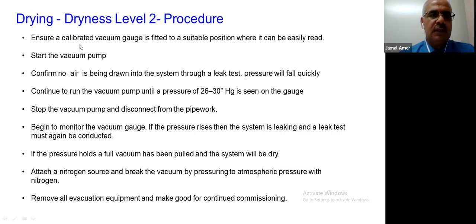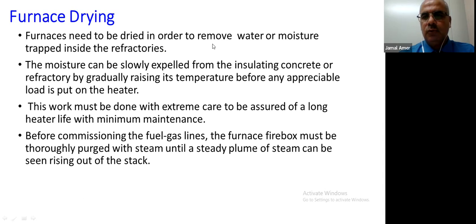Furnace drying. Here regarding furnace drying, the furnace needs to be dried in order to remove water or moisture trapped inside the refractories. The moisture can be slowly expelled from the insulating concrete or refractory by gradually raising its temperature before any appreciable load is put on the heater. This work must be done with extreme care to be assured of a long heater life with minimum maintenance. Before commissioning a fuel gas line, the furnace firebox must be thoroughly purged with steam until a steady column of steam can be seen rising out of the stack.